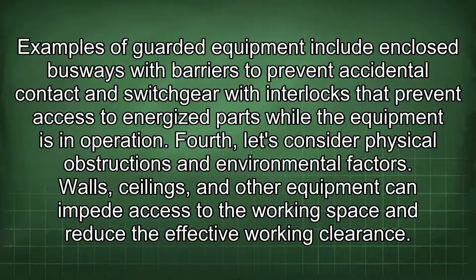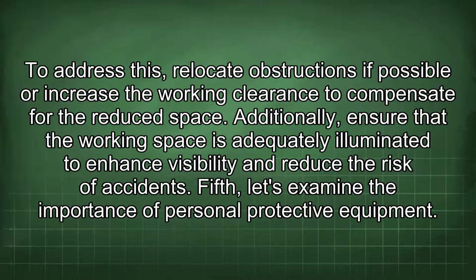Fourth, let's consider physical obstructions and environmental factors. Walls, ceilings, and other equipment can impede access to the working space and reduce the effective working clearance. To address this, relocate obstructions if possible or increase the working clearance to compensate for the reduced space. Additionally, ensure that the working space is adequately illuminated to enhance visibility and reduce the risk of accidents.